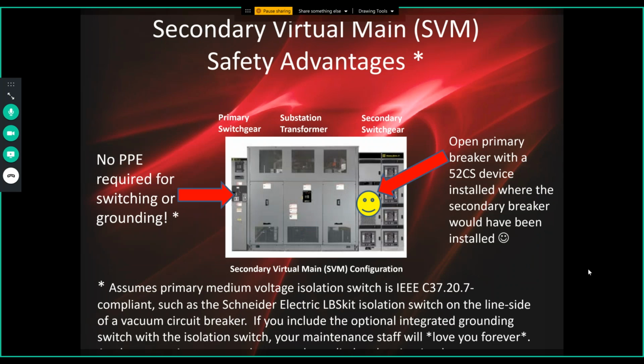So one of the two additional suggestions I would make if you are implementing a secondary virtual main, in terms of the primary switchgear, since that's your lockout tagout point, I would highly recommend an isolation switch, an arc-rated isolation switch that's rated for C37.20.7. What I mean by that is you can operate that isolation switch without any arc-rated PPE requirements. So it's a load break sealed isolation switch.